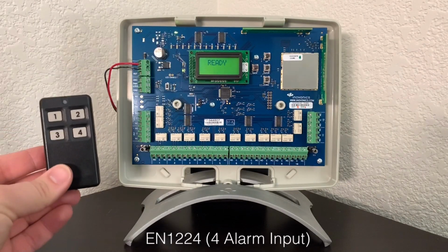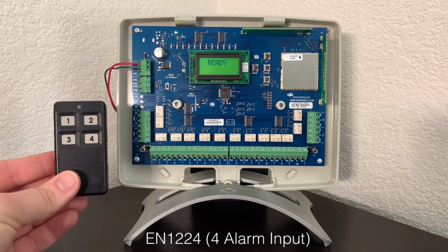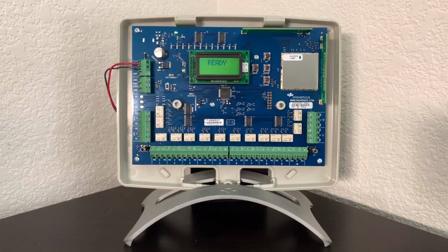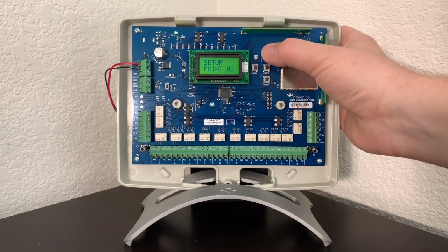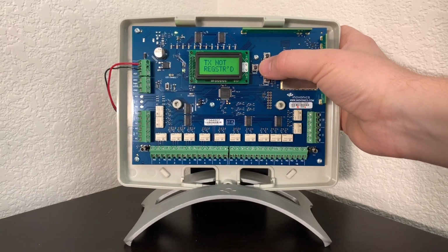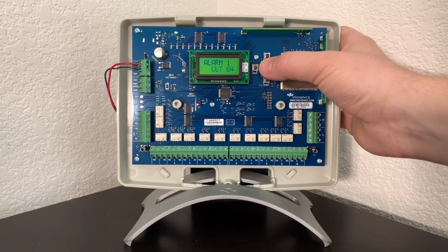For our last example transmitter, we're going to use an EN1224, which is a 4-alarm input device. We'll go back into Setup Point and navigate through the other options. And when we get to alarm input, we're going to select 4 alarm inputs this time. Now, since I've used relays 1 through 3 already, I'm going to have alarm 1 go to relay 4, alarm 2 relay 5.